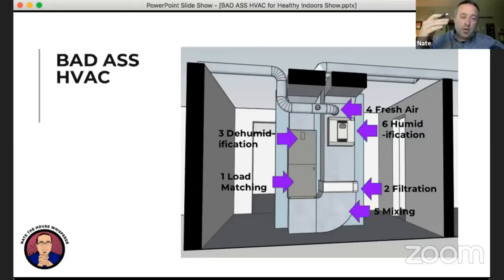If you put in a strong, like a MERV 13 1-inch filter, it's going to create all kinds of pressure where that air is just working hard to try and get through that thing. Where if you use a large filter in the drop and everything's big, that air doesn't work hard to go through there, so we find that we're getting less than 0.1 inch of water column pressure drop across our filters.